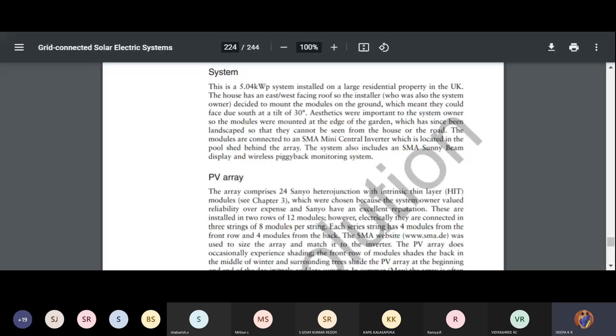Then they are installed in two rows of 12 modules, and electrically they are connected in three strings of 8 modules per string. So this is the electrical diagram, we'll see how it will be. The modules are connected in series, so each series string has 4 modules. Hence you are dividing the system: first you create a string, then you make a parallel connection, and at the back of the system you connect the inverter. So here, use it to size the array and match it to the inverters. Of course, based on the capacity, you need to select the inverter which we are using.